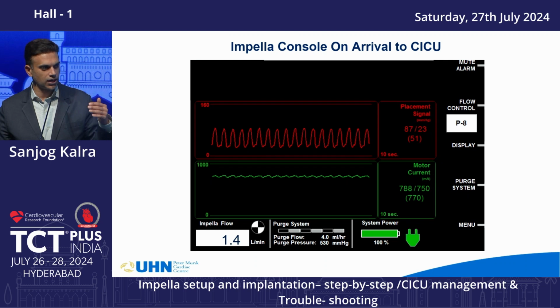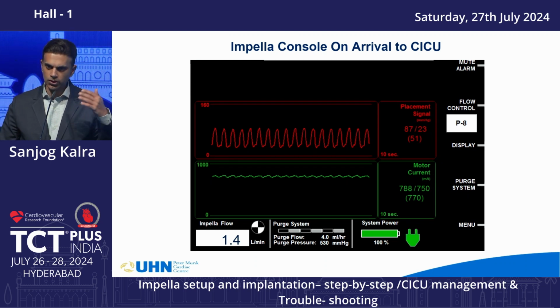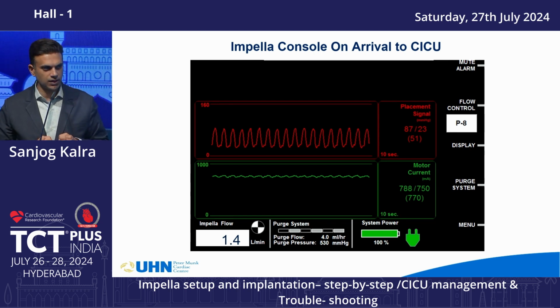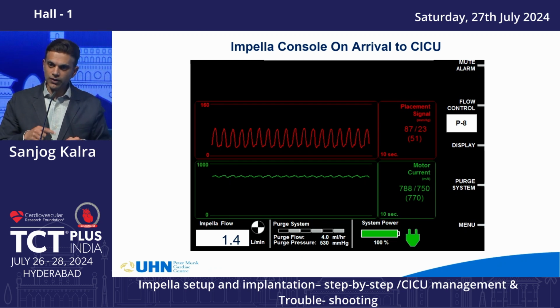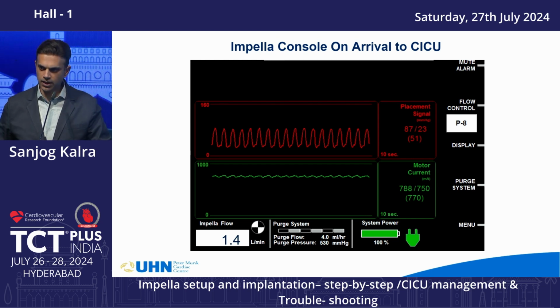This is the motor current. The motor current is a measure of the actual energy the motor is using to move. If you have a device that is contracting in systole and diastole, remembering that this pump is taking blood from the same chamber as is exiting, the motor is going to move a little bit less during systole because the heart's doing some work, and a little bit more during diastole because the heart is not doing much work. So if you have good variability along the motor current, your device is functioning normally. If your motor current, however, is flat, then you have to ask yourself why the pump is not requiring more energy in each phase of the cardiac cycle.